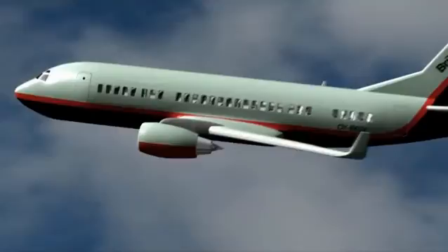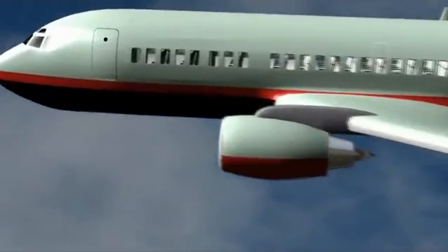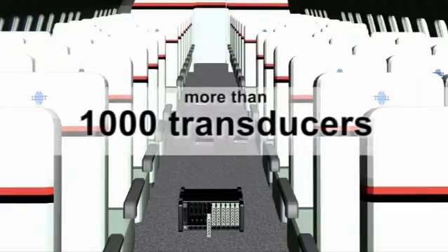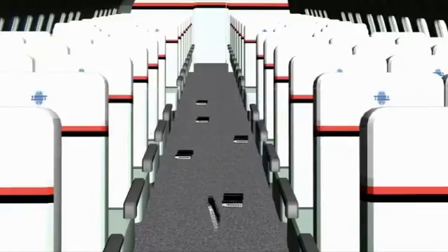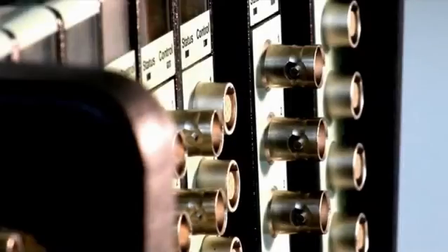Making measurements on an aircraft is no mean feat, but with LAN-XI the task immediately becomes less daunting. The LAN interface allows you to remove the individual modules from the rack and place them close to the measurement object, so you avoid the usual mass of cables and save time into the bargain. And as you're able to connect more than 1,000 transducers, the aircraft is covered in just one measurement, giving you more flexibility while saving time. So no matter how many front-end modules you use, LAN-XI is the answer.